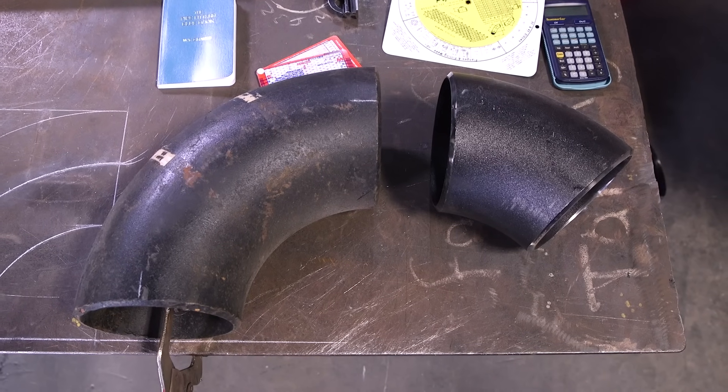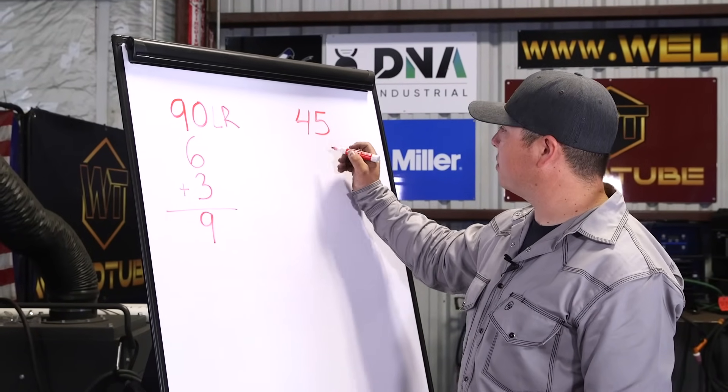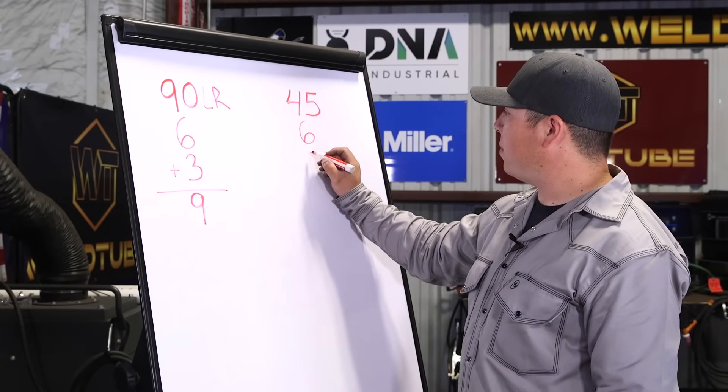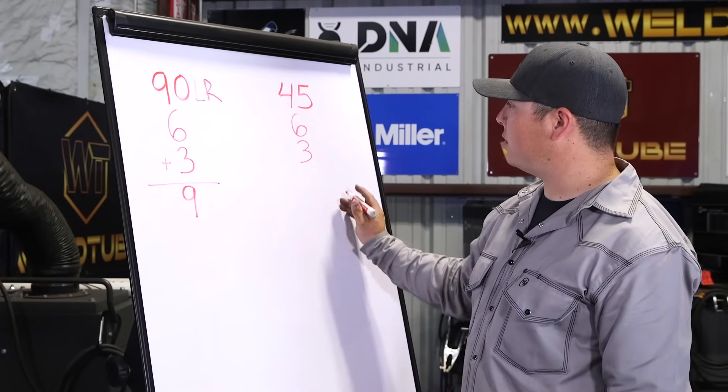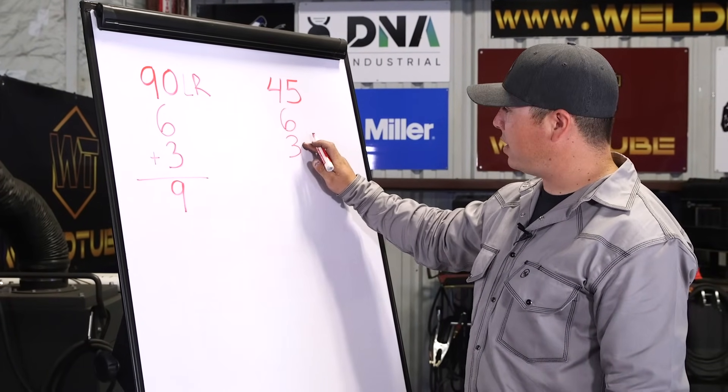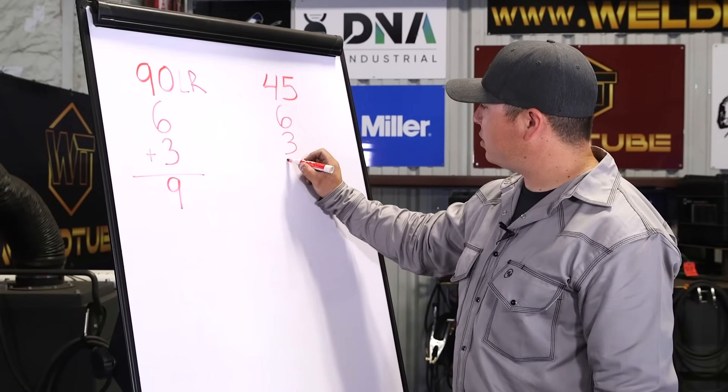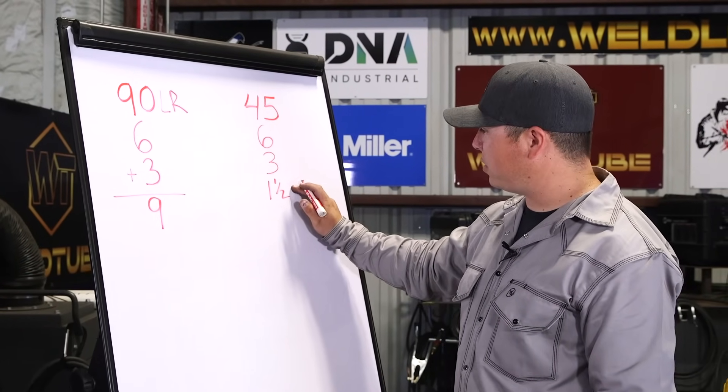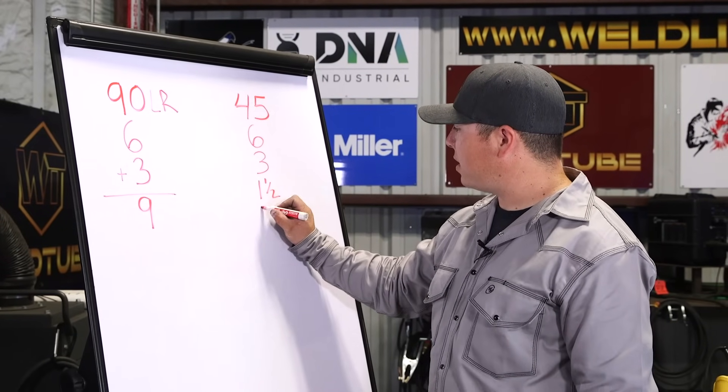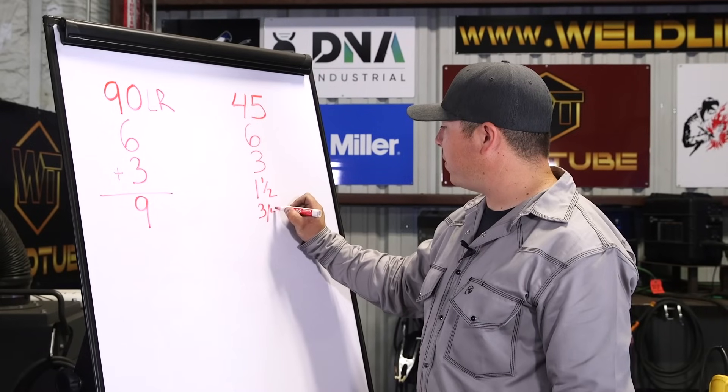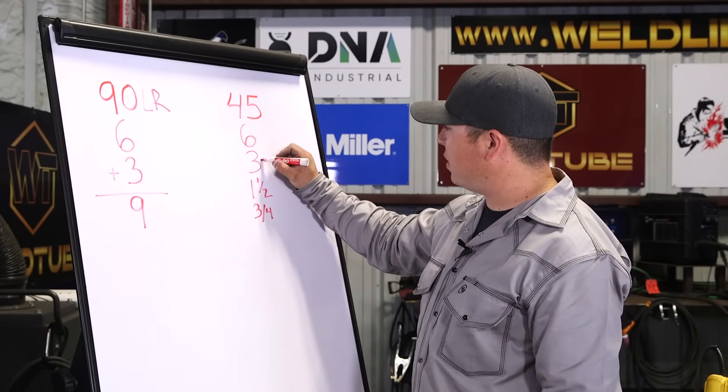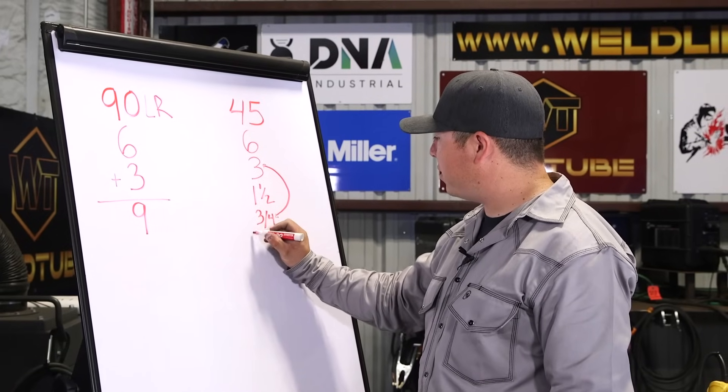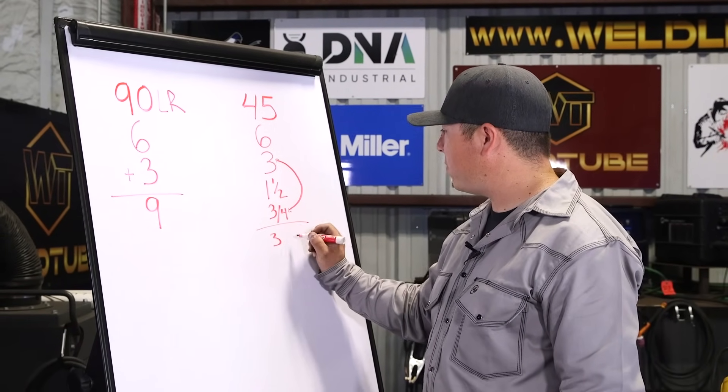And for our 45 degree elbow, we're going to do a very similar process. So we go with our nominal pipe size, which is 6 inches. Break that down in half, that'll give us 3 inches. Same as our 90. We're going to break this down in half again, which will give us one and a half. And now we break this down one more time, and half again, and that'll be 3 quarter. And now we take this number and this number and we add them up. 3 plus 3 quarter, 3 and 3 quarter inches.